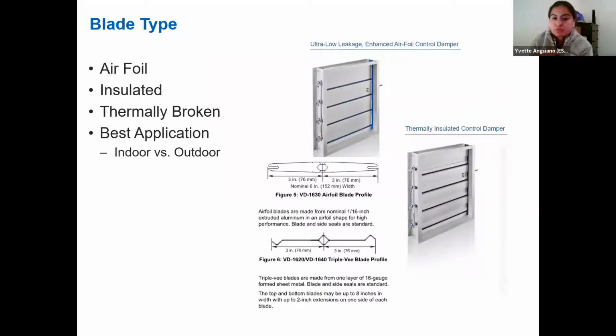And so then getting into blade types. You have two types really, like the airfoil blade profile and then this triple V blade profile. So in terms of that airfoil shape, it's shaped more like an airplane wing, and this blade is kind of more preferred since they have a lower pressure drop across the damper opening due to that more aerodynamic shape of the blade. So overall, we tend to prefer that blade shape in our applications.